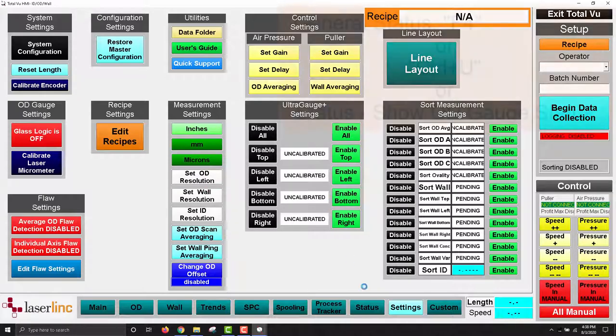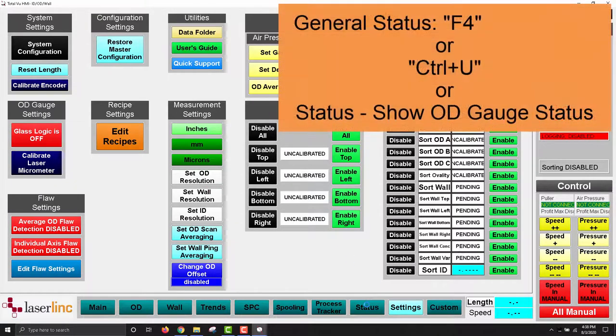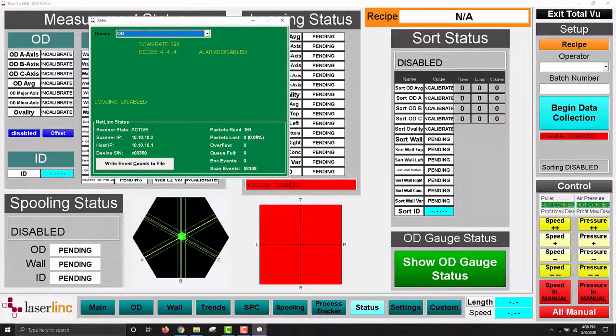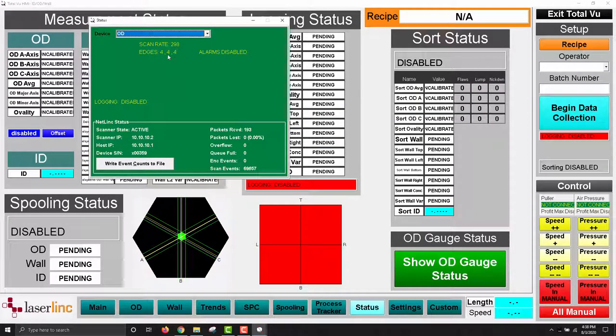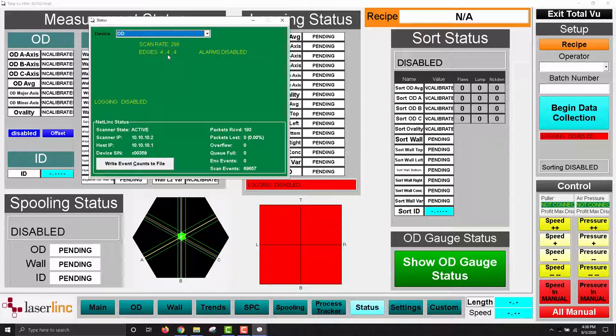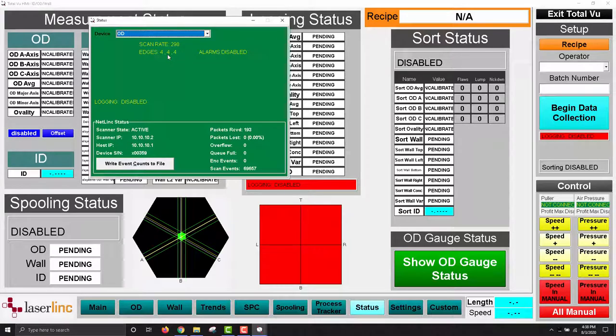Exit out of the full configuration menu, then press the F4 function key or the Control-U key combination to open the general status window. Select your gauge from the drop-down at the top of the window. If the gauge is communicating properly, we should see two edges for each axis when nothing is in the field. If you put something in the field, for example your finger, you should see the edge count increase to 4 for each axis. The reported measurement rate should be steady as well. The measurement rate depends on the model of the gauge. Please visit our website at www.laserlinc.com forward slash products and choose the gauge you have to view its measurement rate and additional details.